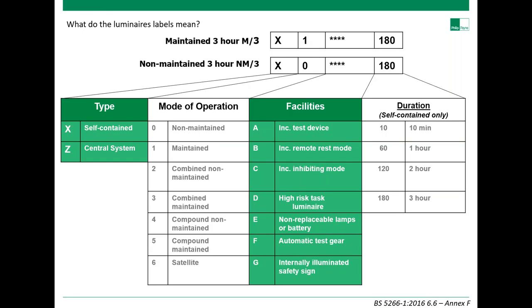What do luminaire labels mean? Manufacturers package their products in accordance with a labelling system. Looking at the columns: type X denotes self-contained. For example, a self-contained DALI non-maintained product with a three-hour duration would read X, 0, A, B, C, F, 180. Three hours is the norm in the UK and parts of Europe. The duration of emergency lighting must be decided before detailed design is commenced — EN 1838 specifies one hour minimum, but BS 5266 Part 1 expands this, stating one hour should only be used where premises are immediately evacuated on power failure and not reoccupied until the system is back to full capacity, which would delay reoccupation for many hours.